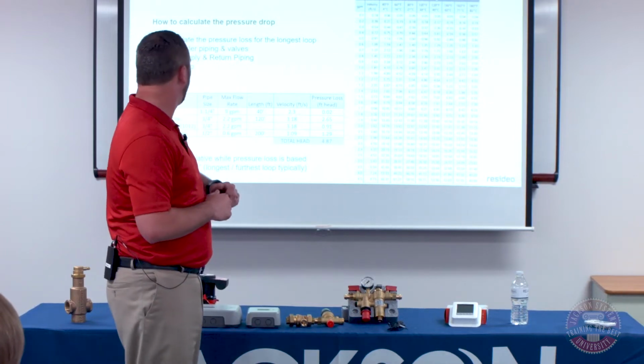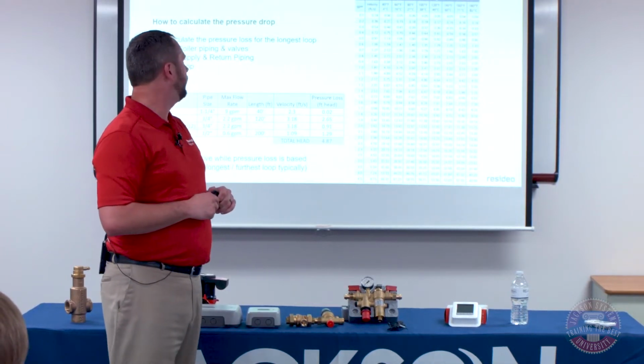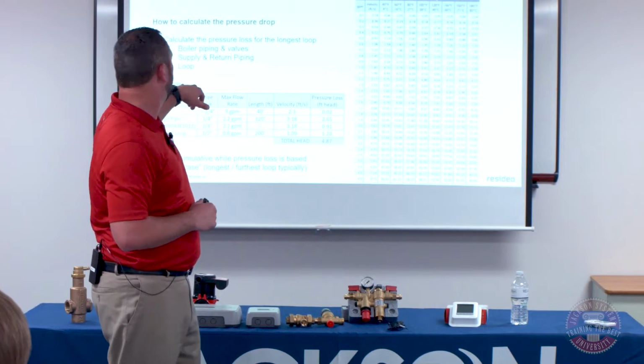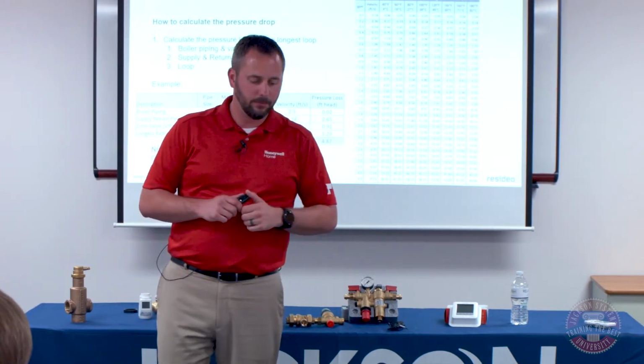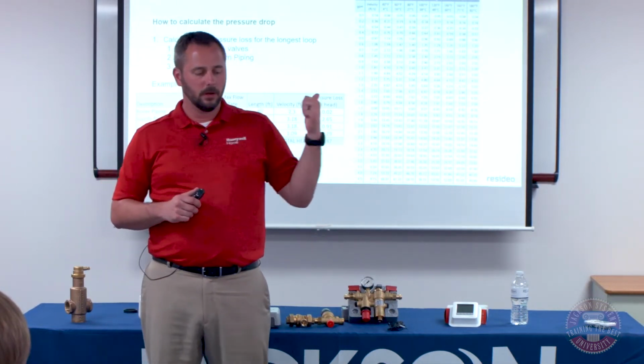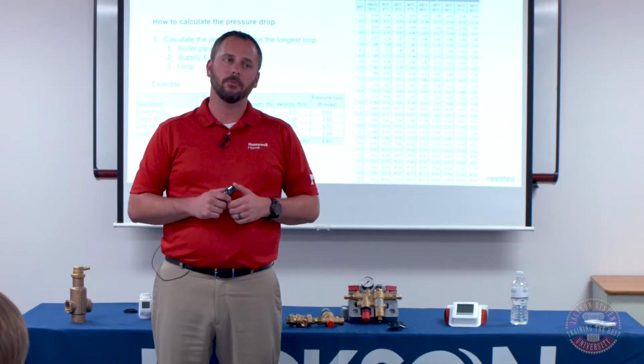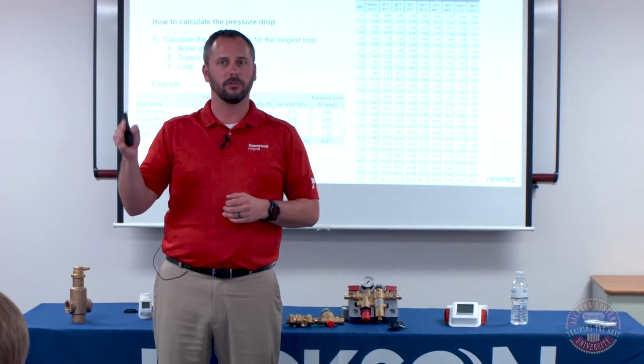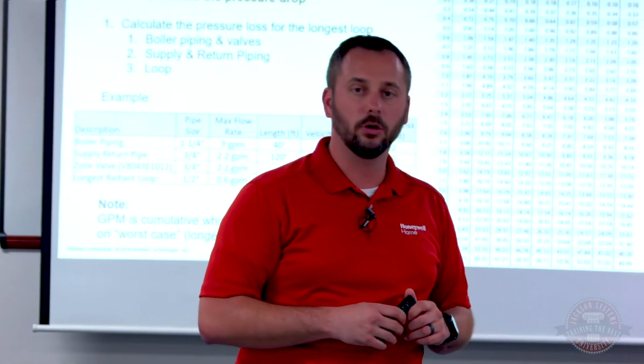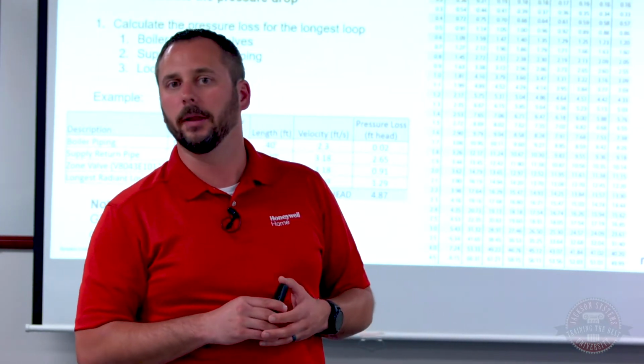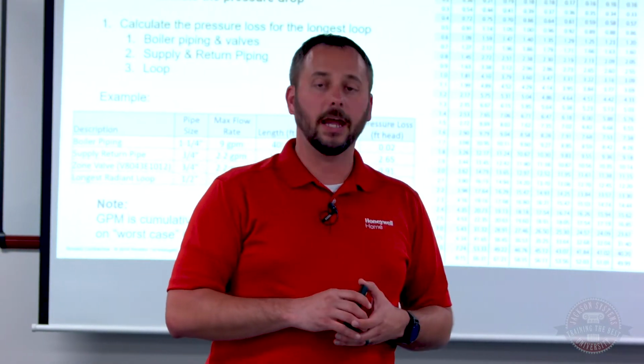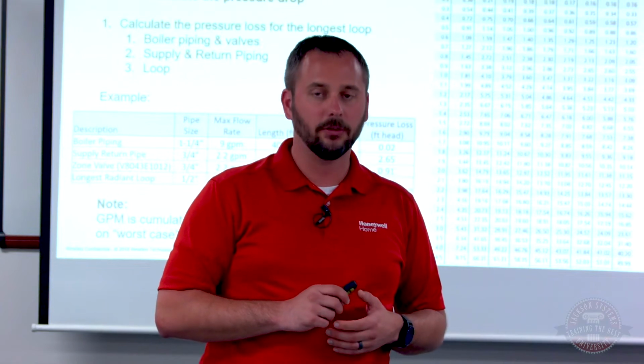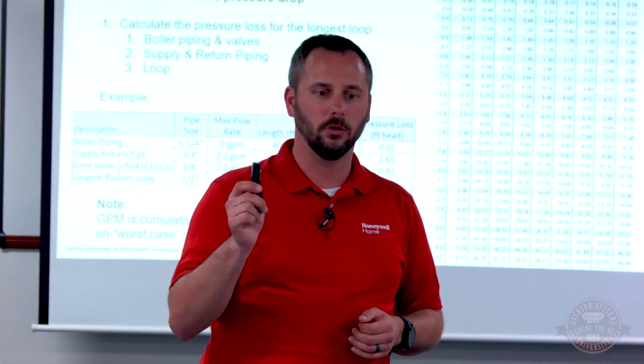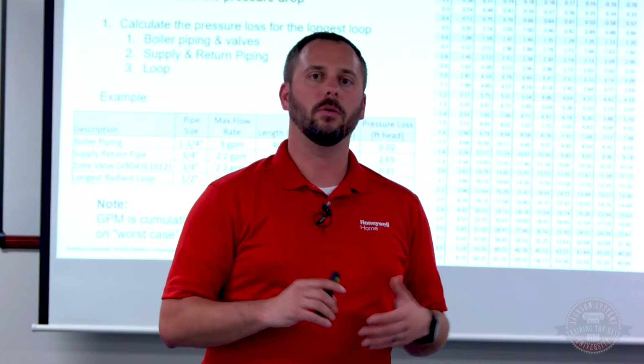So in this example, we're running the system, I believe, at, I went through on boiler piping, did 1.25 inch pipe, 9 gallons a minute. I did system return pipe, so that 9-gallon system has multiple zones. So the first zone that we're going through, we're driving 2.2 gallons a minute through it. Then we've got to go through a zone valve, and I'll talk about zone valves and flow coefficients too. But we're going through a zone valve, and then we've got the longest loop.